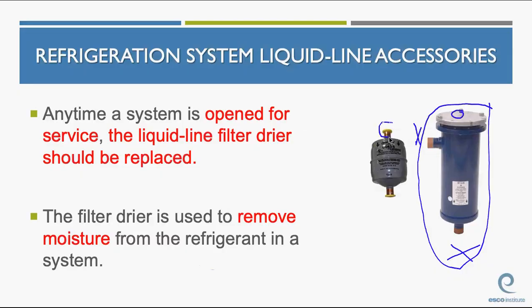This type of filter dryer here, I actually have to braze in and out. So I try not to open refrigerant systems as much as possible. That's why a lot of times in our shops we put in filter dryers that have flare fittings on them, because sooner or later you're going to run out of line set to braze these into. Two different types of filter dryers, same basic thing. This is more often the type you'd find on the suction side as a cleanup filter dryer.